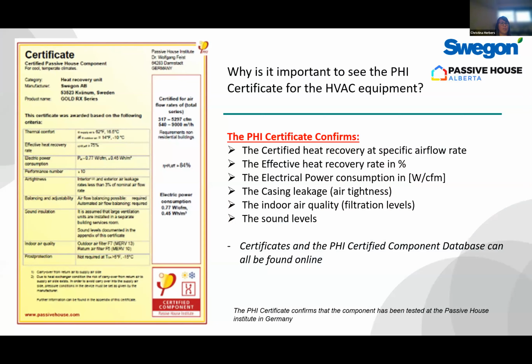And so, why would it be important to see a Passive House certificate for the HVAC equipment if you're pursuing that Passive House rating? Well, the Passive House certificate confirms that the component has been tested at the Passive House Institute in Germany. And it confirms that the certified heat recovery rate is accurate and has been tested. The efficiency of the heat recovery rate, the electrical power consumption in watts per CFM, and the air tightness are at an acceptable level. Kevin mentioned that. And the indoor air quality, the filtration levels, and the sound levels are at the acceptable Passive House level. So really keep that in mind when you're doing your projects: the Passive House Institute certificate is really important for your mechanical equipment.